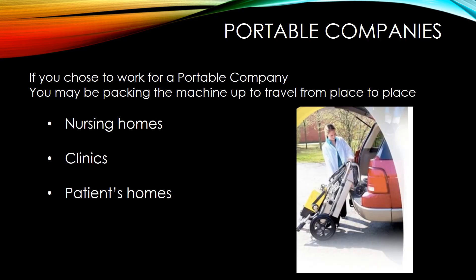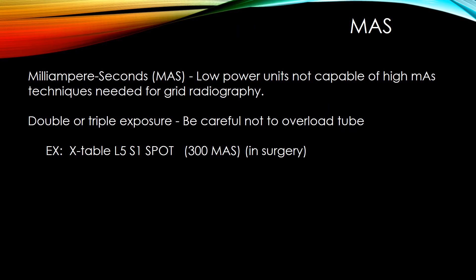If you choose to work for a portable company, you may be packing up a machine that is able to travel from place to place — like nursing homes, clinics, and patients' homes. These types of x-ray equipment are able to come apart so you can put them in the back of your vehicle. Regarding mAs: low power units are not capable of high mAs techniques for grid radiography. You may need to double or triple exposure. Be careful — do not overload the tube. For example, an L5-S1 spot film in the OR would need 300 mAs.